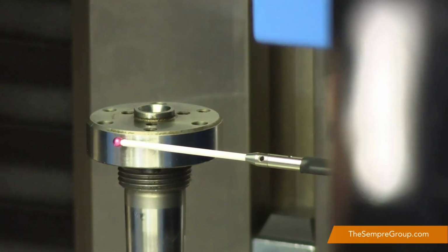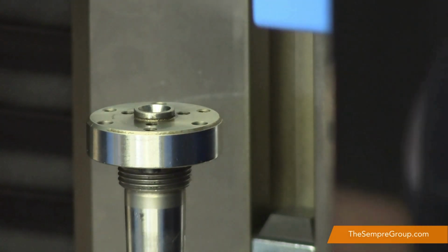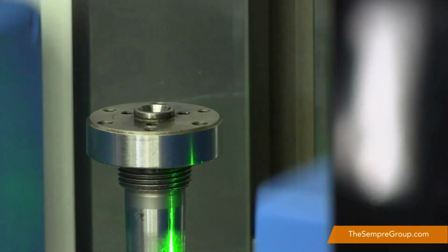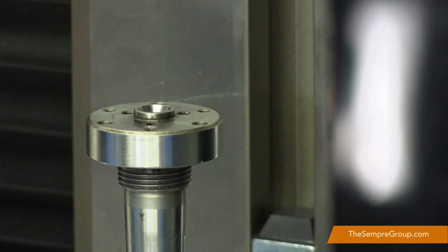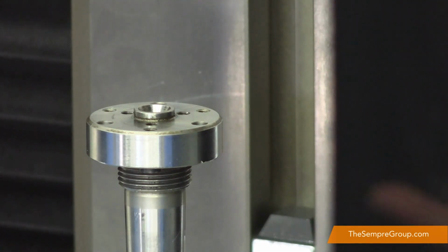So you can see the first measurement. This is the more manufactured one, as such. I'm just measuring the external chamfer length. I could do that with the optics in this scenario, but what we're going to do is just show you the principle really.